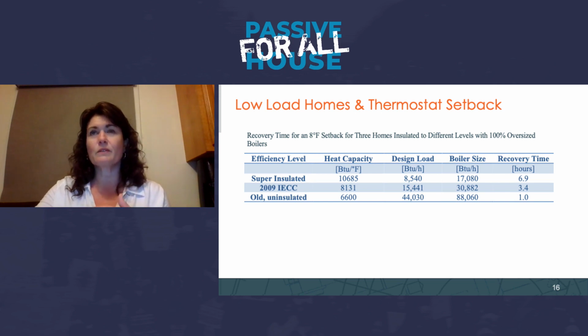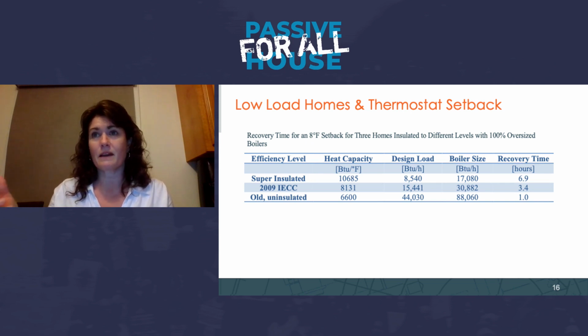This is also going to apply to some of our multifamily buildings. However, keep in mind that the design heat load for an apartment is 800 to 1,000 BTUs per hour. It's small, going to be less than that even. So even with a 6,000 BTU minimum evap inside the apartment, we're still like 6 times oversized for heating. So you can recover quickly in a multifamily apartment.